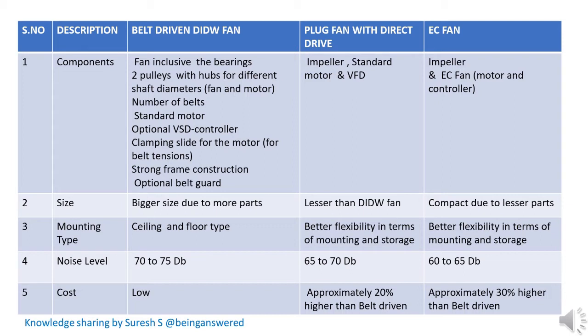The major point is noise level. Belt driven DIDW fan will have 70 to 75 decibels. Plug fan will have 65 to 70 decibels, whereas EC fan will have 60 to 65 decibels. This might get reduced again depending upon the thickness of the outer skin and moreover depends upon the manufacturer also.